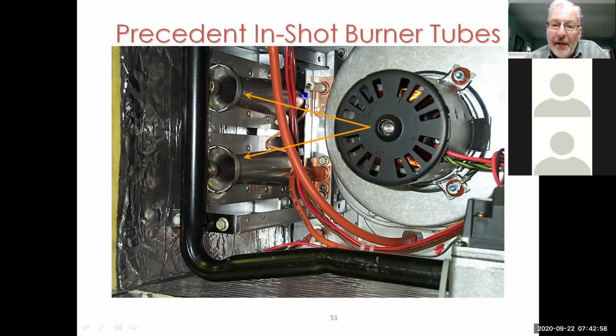Also, what you're going to see on these systems is about 50 to 60 volts on this sensor right here. That's a reference voltage. So as soon as the flame comes on, we start to pass current through that flame to the face of the burner. And there should be 60 volts here. We should have the 2.5 microamps. Again, clean burners, make sure we got a good ground on the system. All of the simple little things that you look for when you're doing a maintenance on these units.